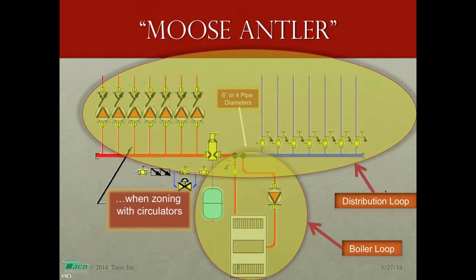Ryan O'Connell asked a good question. The indirect goes directly off of the boiler loop. Yes, if you were to pipe an indirect water heater, you'd go off of the supply and return on the boiler loop. What would happen is when you have domestic hot water priority, the boiler circulator will shut down, so we're not sending any water to the distribution loop, and the indirect circulator would take over, and all of the flow would be directed to the indirect. So excellent, good question, Ryan. Thanks, man. I hope that answered your question.